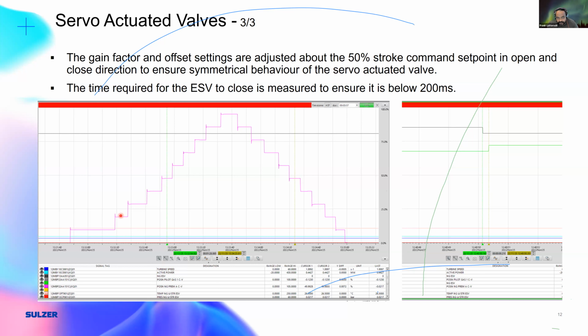Such that when you have a step response, meaning you give a certain command set point, 10% steps from 0 to 100, I want to see the valve perform one overswing and no underswing. And on my way down, I expect only one underswing and no overswing. So that would be the gain factor. So in a PID controller setup, your P constant is, in this case, a gain factor. The I would be the integration over time. We don't have a D because we want to have it quite fast and responsive.